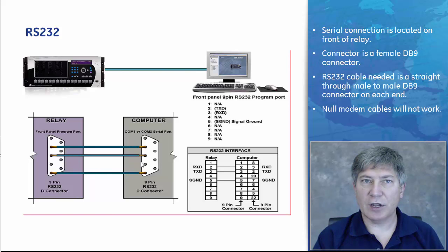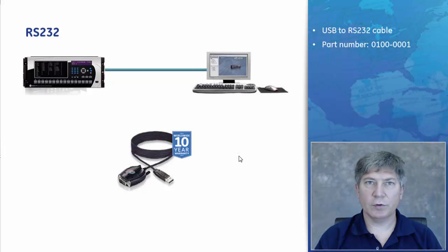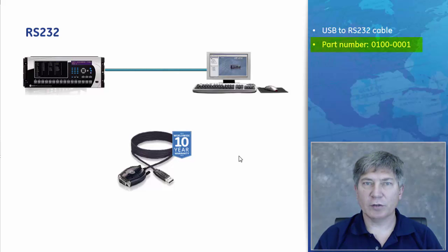Three signals are used in the 9-pin connector: Pin 2 connects to pin 2, pin 3 to pin 3, and pin 5 to pin 5. A null modem cable connecting pin 2 to pin 3 of the other end will not work. For newer computers without a serial connection, the USB port can be used with an RS-232 USB cable available from our online store, part number 0100-0001. This cable has a Windows driver that needs to be installed before use.